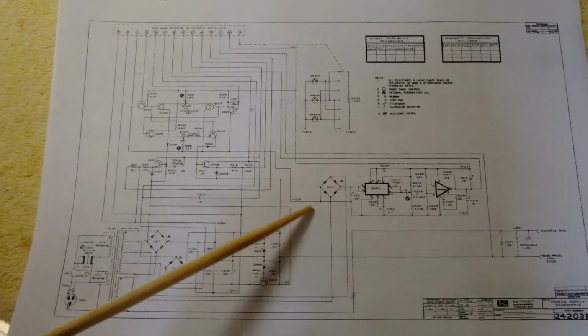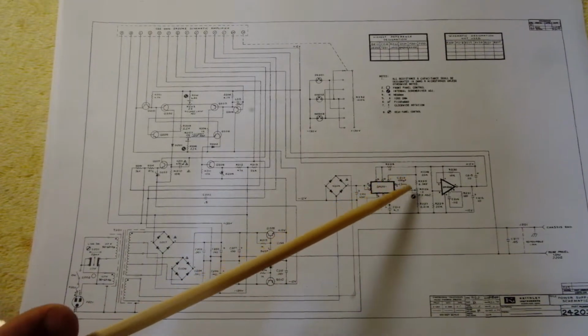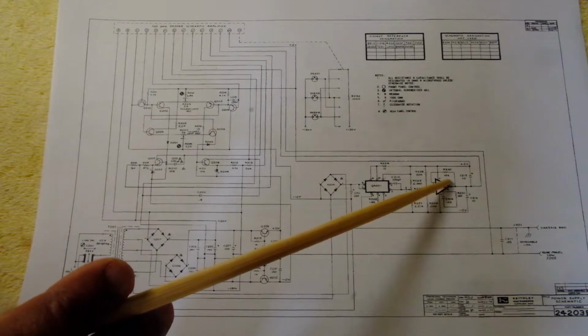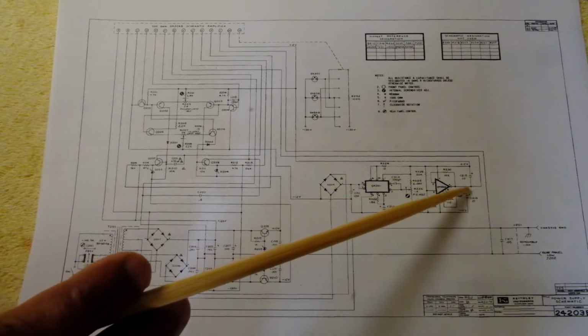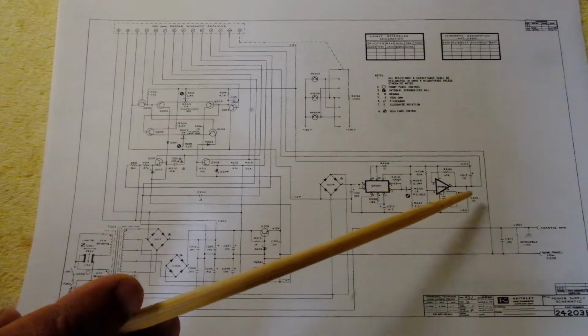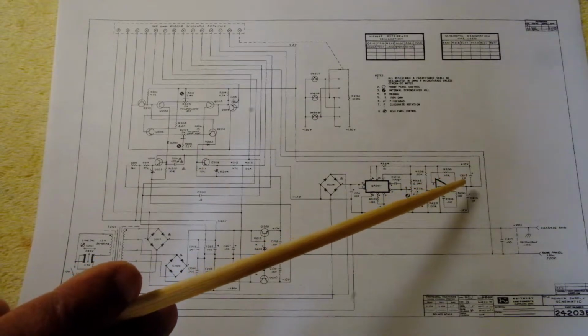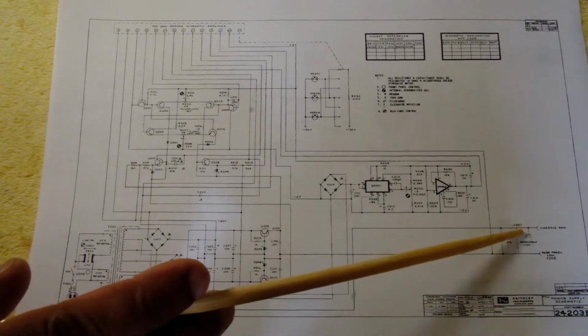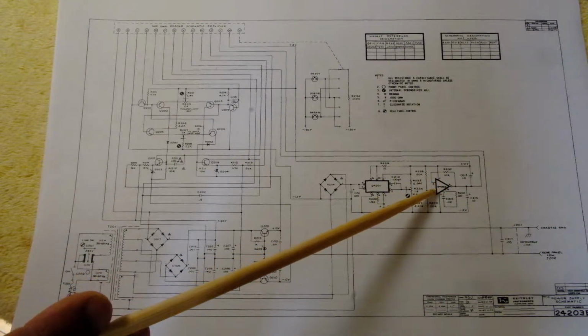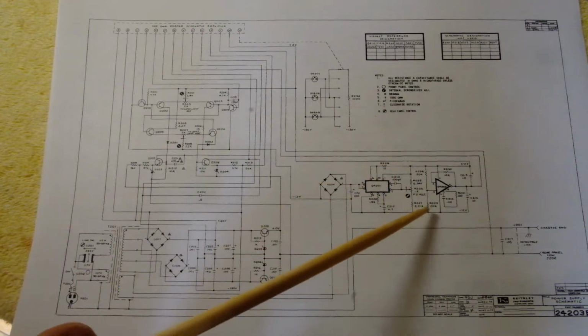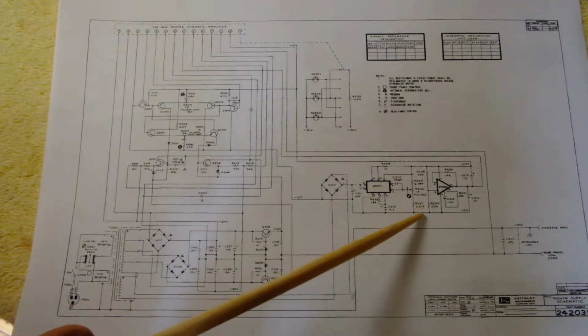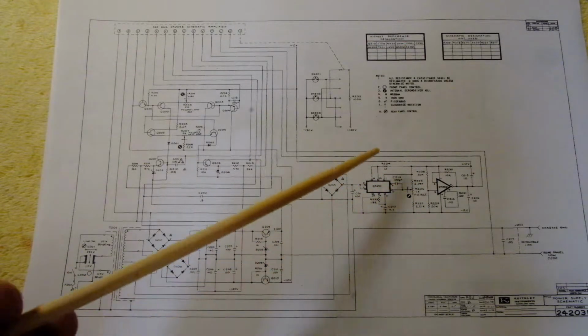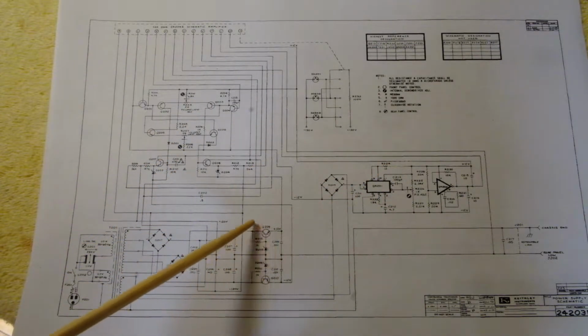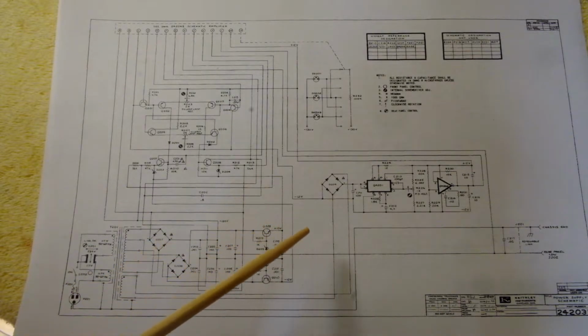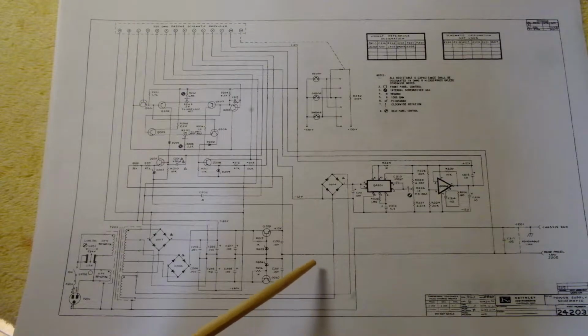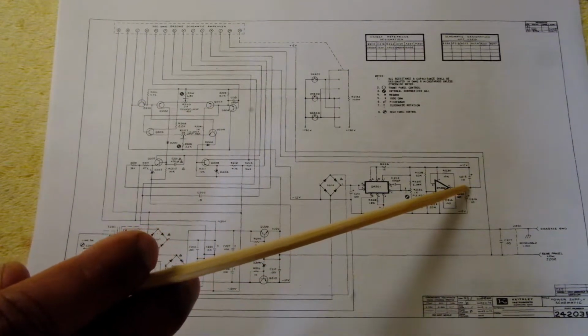Since there is no ground reference in this particular supply, that is, it is entirely floating, the ground is really determined by this amplifier, and this amplifier has to be able to drive this ground common, or the common terminal, all over this instrument to 0 volts and keep it there. It's basically independent of the earth or the low ground, which is the output of this instrument. So if this amplifier fails, then basically nothing works. This output could float to anything, any voltage. It could go to 100 volts, minus 100 volts, or any voltage in between the rails that is generated by the plus minus 130 volt supply. Because if you look at the overall block diagram, the plus minus 130 volt reference common point is really the output of this amplifier, which is a common node.